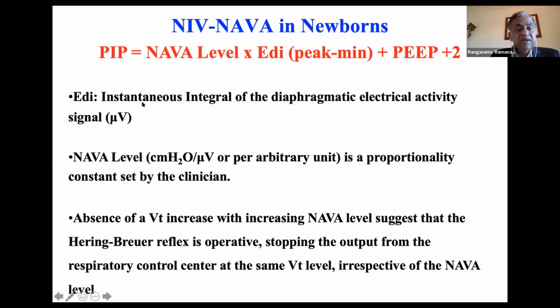EDI is the instantaneous integral of the diaphragmatic electrical activity, expressed in microvolts. NAVA level, as I mentioned, is centimeters of water per microvolt. It's an arbitrary unit, a proportionality constant set by the clinician. Absence of a tidal volume increase with increasing NAVA level suggests that the Hering-Breuer reflex is operative, stopping the output from the respiratory control center at the same tidal volume level, whatever NAVA level you are setting. Let me make it a little bit more clear.